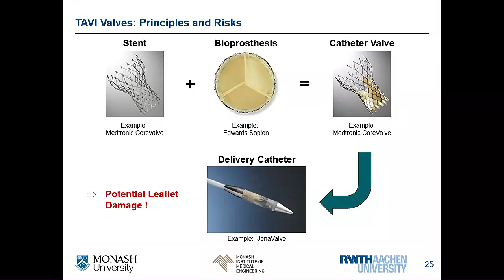There are many other risks associated, but just as an example, we have a degraded valve durability as a hazard. The event that caused that was damage in the crimping process. So the hazardous situation is that the leaflets tear, they rupture a little bit, and they don't really close anymore, or that they calcify. These valves tend, after time in the body, to calcify, that calcium is deposited.